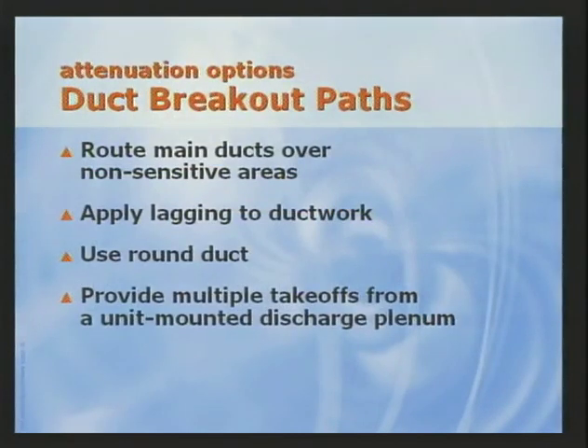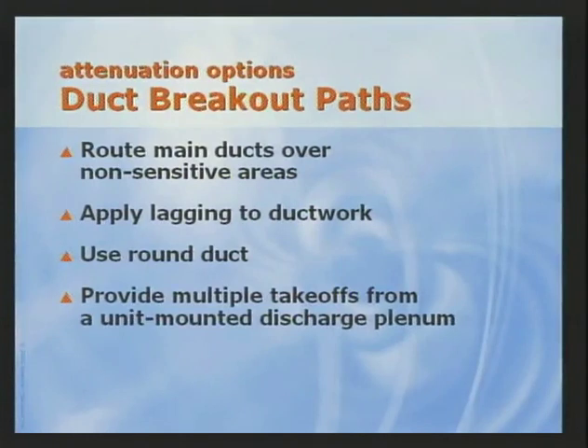When main supply or return ducts must be routed over sound-sensitive areas, duct breakout can be reduced by duct lagging, round duct, or using multiple takeoffs from a plenum on the unit. Duct lagging involves wrapping the duct with gypsum board or some other dense material to increase the transmission loss through the duct wall. Round duct is much stiffer than rectangular or flat oval duct and naturally has a high transmission loss. The problem generally encountered with round duct is having sufficient space in the ceiling plenum. Using multiple taps from a plenum on the air handling unit can help with the round duct space problem. And it also splits the sound at the source so that there is less sound pressure in each of the ducts. By routing the takeoffs in different directions, no one area is exposed to the total sound potential of the supply.